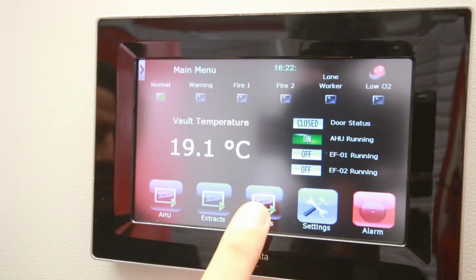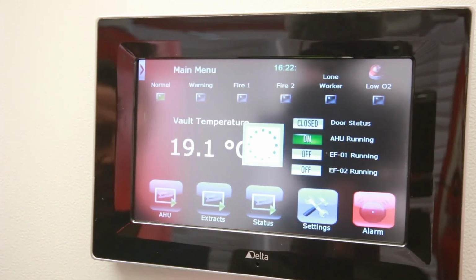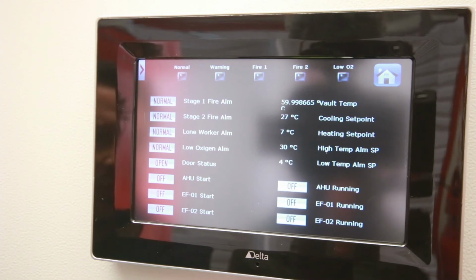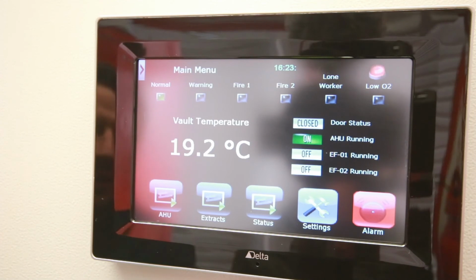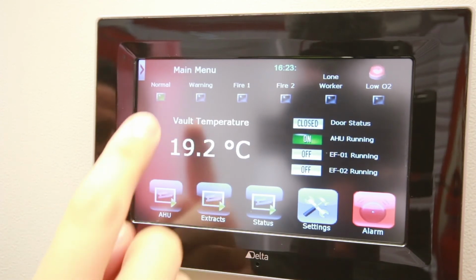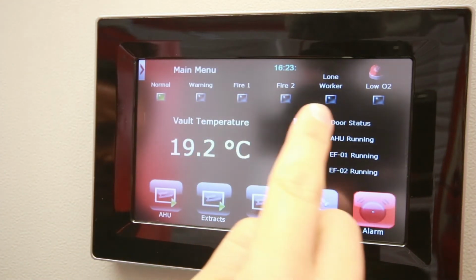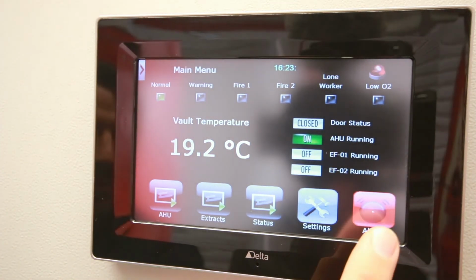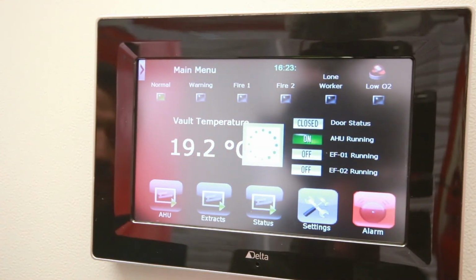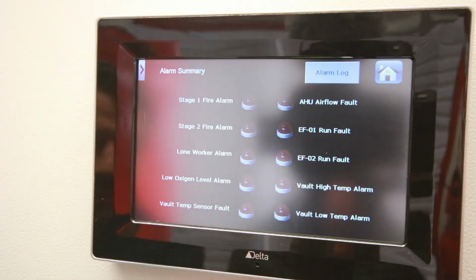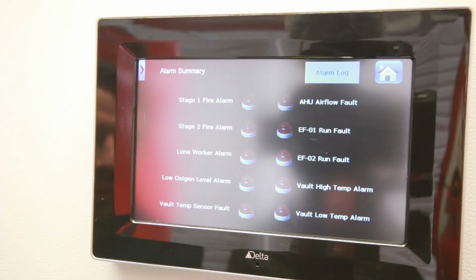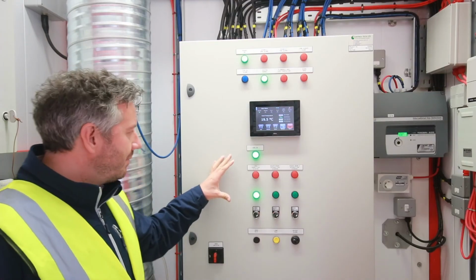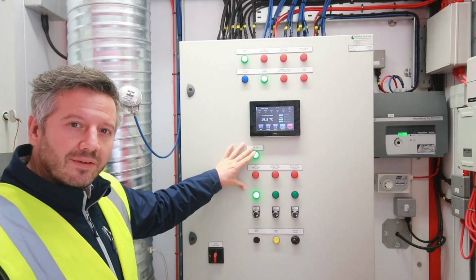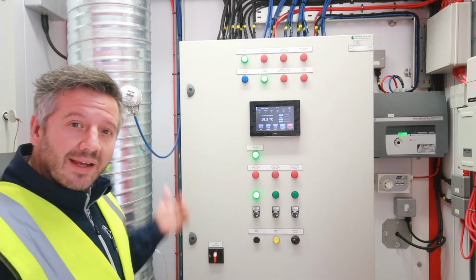The status menu offers more information than is shown on the home screen. Should you find the system in alarm mode, or if any of these square indicators turn red, the alarm menu can be found here. This lists all the alarms of the system and will clearly indicate what feature is indicating alarm. Okay, below the Delta controller, we have the airflow indicator to prove that there's circulating air currently.